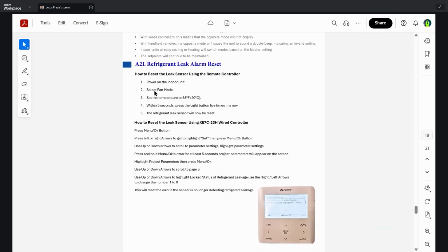Moving along, the A2L refrigerant leak alarm reset. Below is the illustration on how to reset the A2L alarm if it ever trips. So what you're going to do is you're going to power on the indoor unit, select fan mode, set the temperature to 68 degrees Fahrenheit, and within 5 seconds of doing that, press the light button 5 times in a row. And we know that this will actually reset the refrigerant leak sensor.